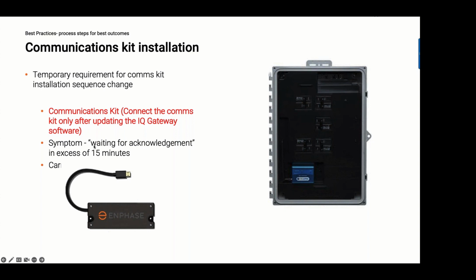So the thing that we want you to do is when you are bringing the system up, you need to update the Envoy software from your phone. Remember, the phone is getting the latest software and then it's going to update the system. When you are updating the Envoy software, you want to make sure that this communications kit is actually unplugged. So that means that you bring the system up, you connect your phone using AP mode, you download and update the software in the Envoy, and you do that with the comms kit unplugged. After you've updated the Envoy software, then you go ahead and plug your comms kit in and continue the system commissioning.